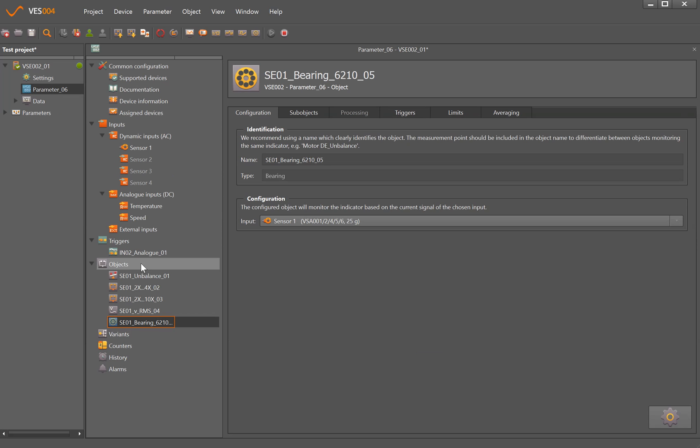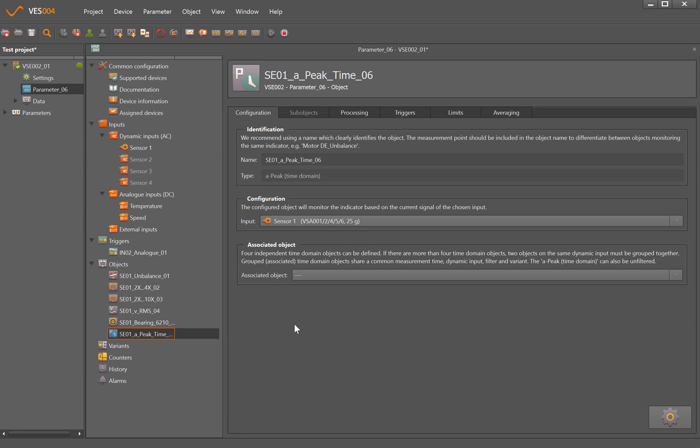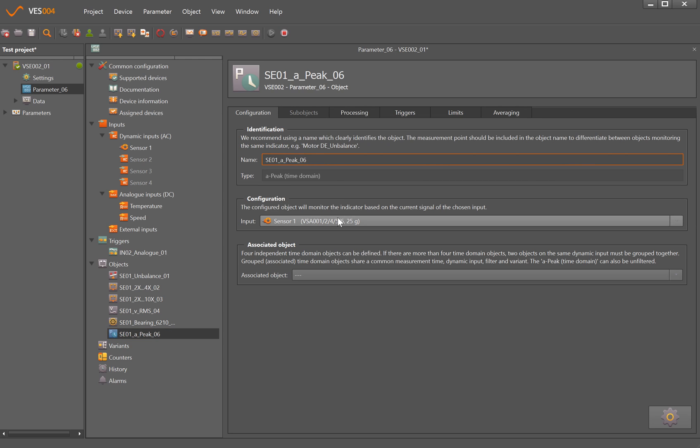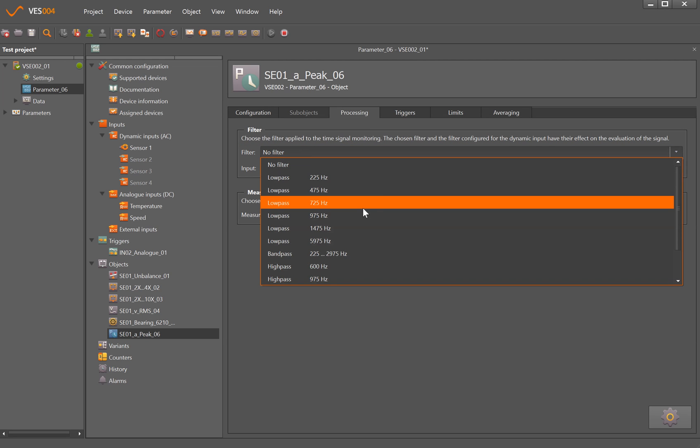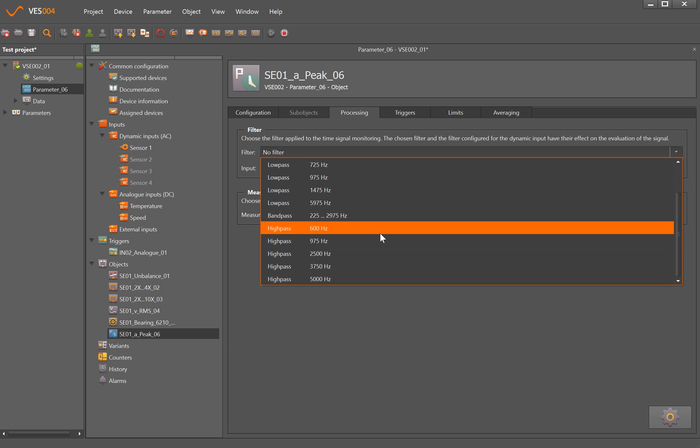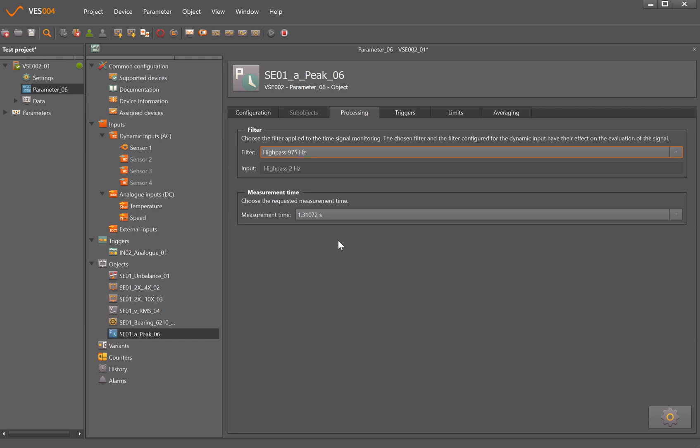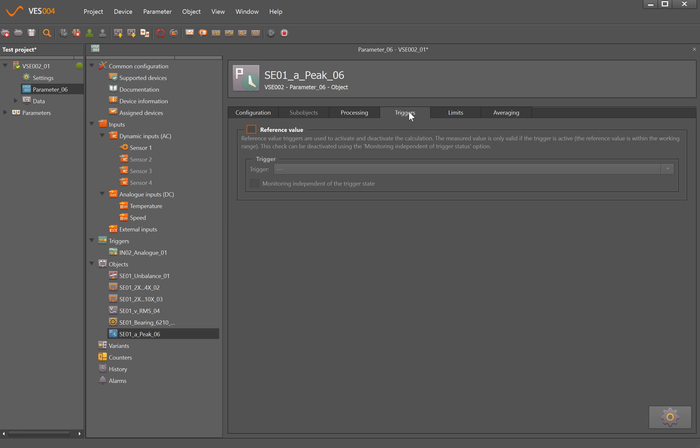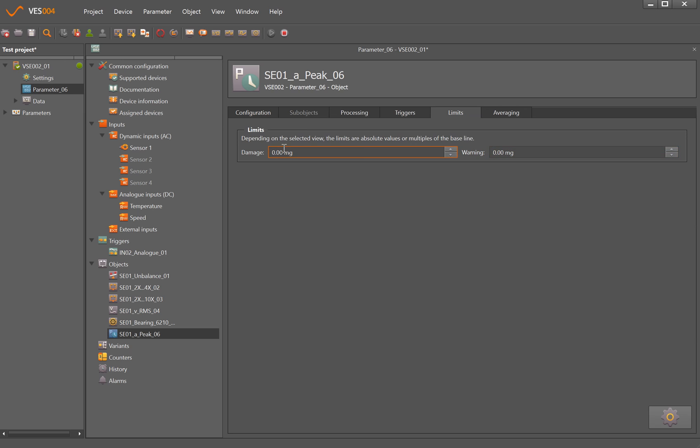We will also look for peak acceleration, so this is looking for the maximum acceleration level either in a positive or negative direction and calculating based on that. So I'm just going to remove the time for neatness. So it's on sensor one processing, we can have no filter, there's various high pass, low pass, band pass filters. So I'll maybe just set a high pass say 975 hertz. There's no triggering there because it's just looking at that frequency range regardless of speed. The levels, say if I wanted to put maybe, so these are milliG's, so say four thousand milliG's so four G's, and maybe two thousand for that. And if we want to do averaging as well, again we can put that in there also.